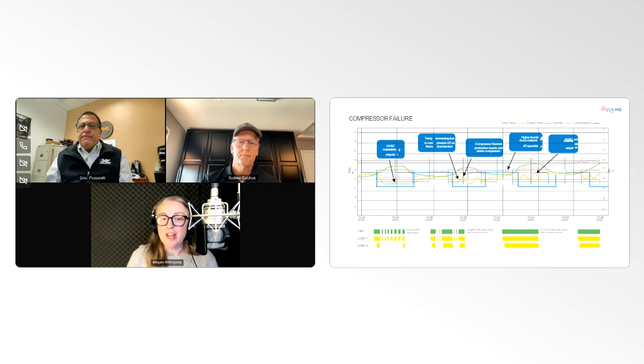So let's move on to the next one then. Gino, can you tell me about the signs of an HVAC failure due to electrical problems? Electrical problems, probably the number one is a tripped breaker. There's a lot of items that go into a breaker tripping.